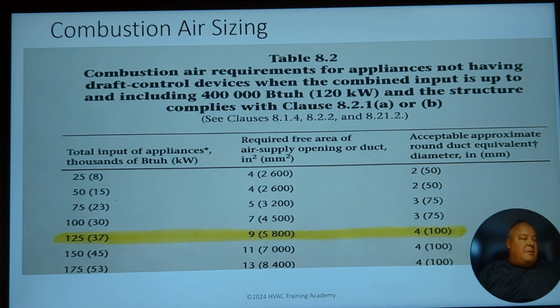We're going to have 9 square inches on the fan-assisted appliances. The 4-inch round, you might say, okay, well, it was 5 the last time. You're going to find that because of the amount of area of a circle, that number is not going to be half like it was 5 the last time. It's going to be 2.5 inches now. It's going to be a way different equation. But your square opening will be half as much. And again, that's the one I'd really worry about in this application.